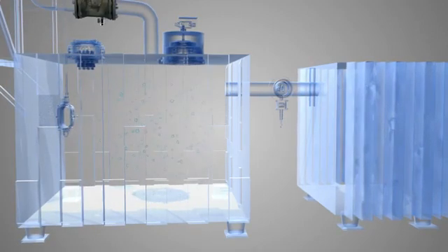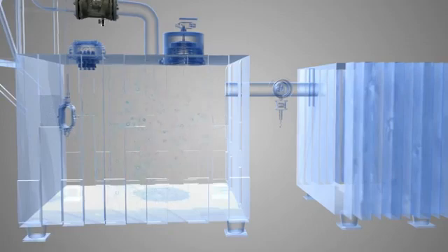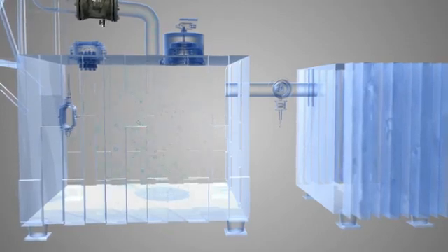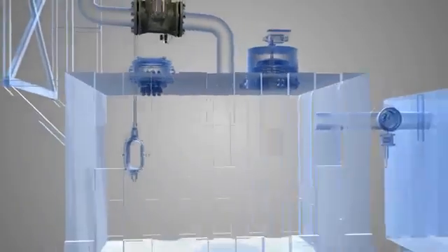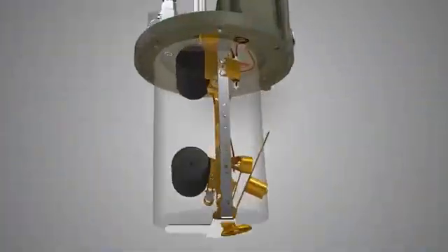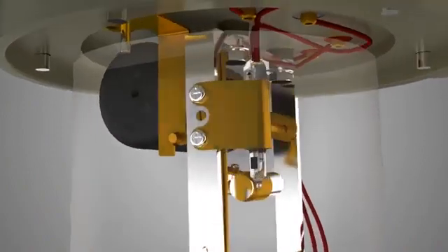Such decomposition generates small gas bubbles which will pass upward towards the conservator. Generated gas gets collected in the Buchholz relay, making the oil level to fall.